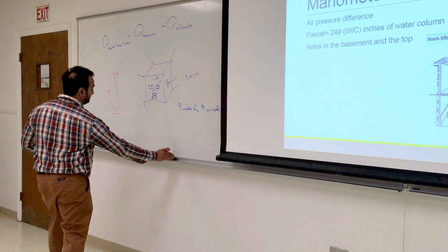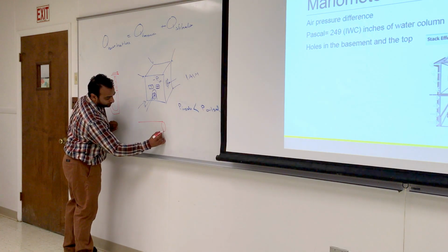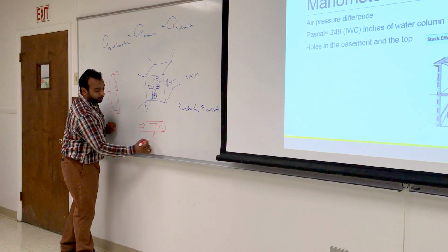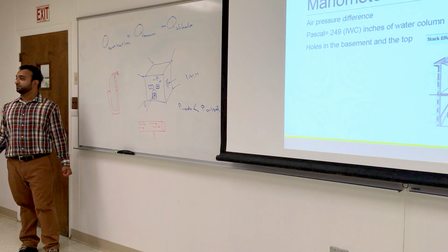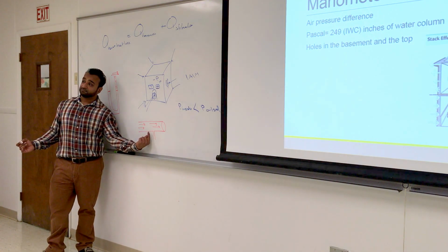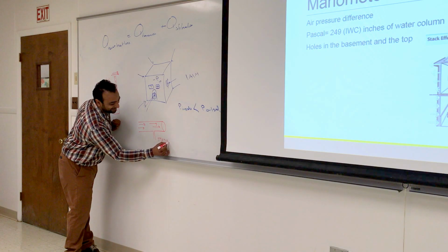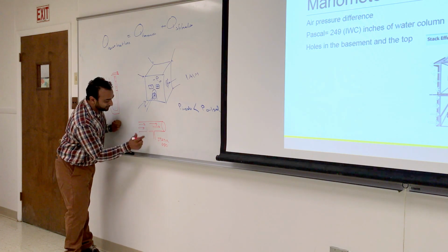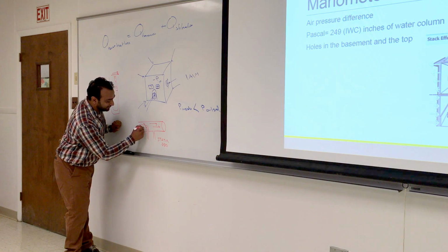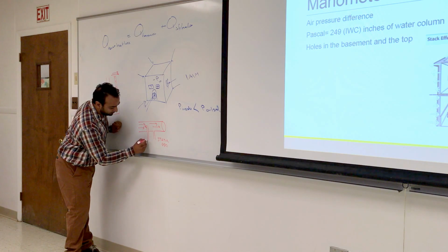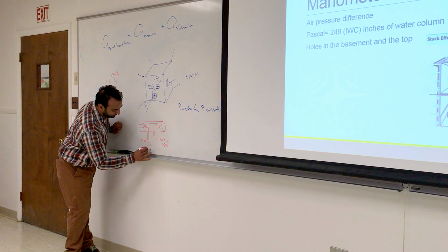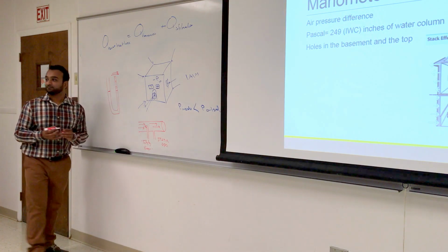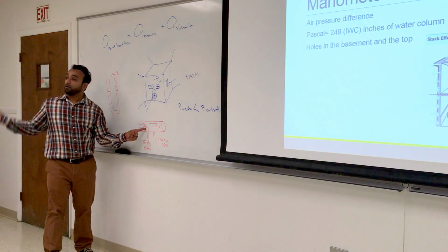So, in a smaller example, we have a duct system with air flowing through it. If we put a manometer here, what do we get? Static pressure or velocity pressure? Velocity. No, it's on the side. Oh, okay. That's going to be static pressure. I know it's confusing. And if we put a tube in here, facing the other way, that's velocity. Actually, I'm wrong. This is total pressure, because this is also getting some static and also getting velocity.